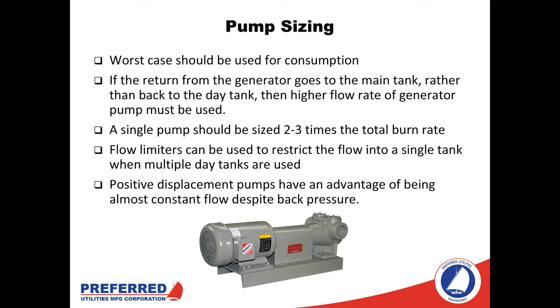Now we've covered fuel storage quantities. The next point is sizing the pumps — how fast does fuel need to move from one point to another? Worst case is used for consumption: we assume generators are fully loaded and all are calling at the same time. A single pump would be sized about two to three times the total burn rate, depending on system size. Flow limiters can restrict flow into a single day tank when multiple day tanks are used. In a real-life situation with a single duplex transfer pump set and 10 day tanks, often only one day tank inlet valve will be open and calling for fuel at a given time.